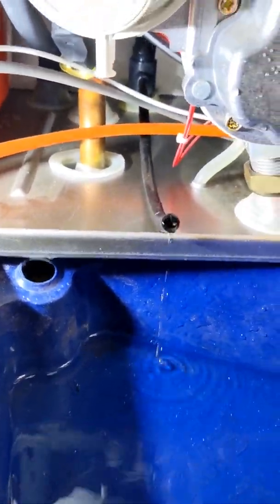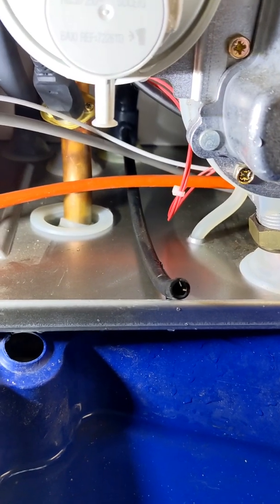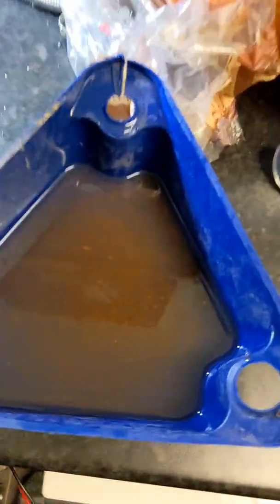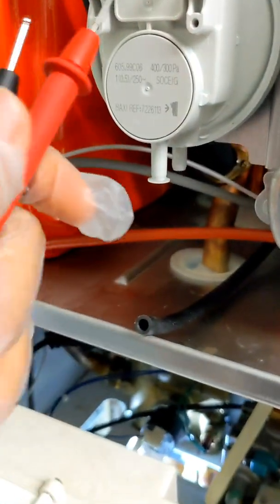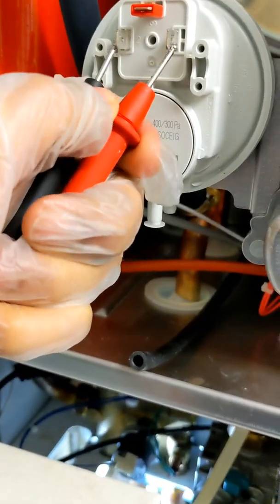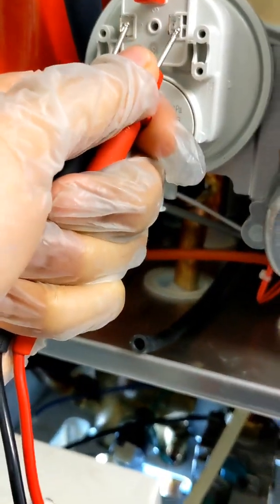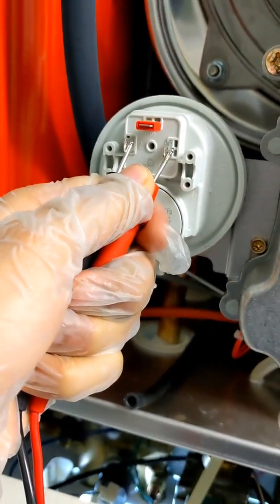So I'm going to take out the trap now and see where it's blocked further down. That's all the stuff that came out of the condensate trap. Now that my air pressure switch is empty, it's not full of condensate anymore. Let's get these back on. Right, there we go. Got my continuity.